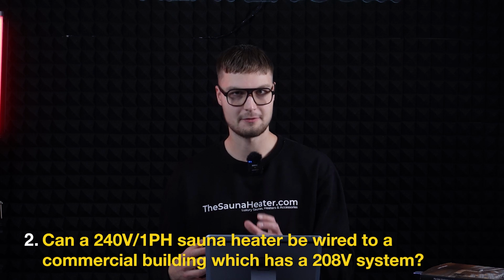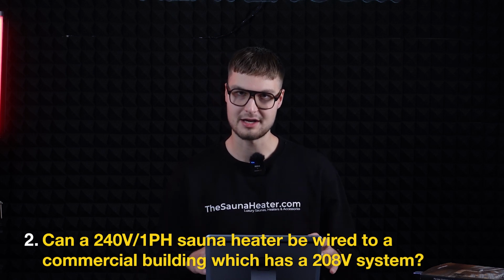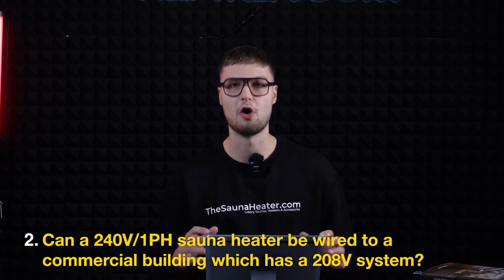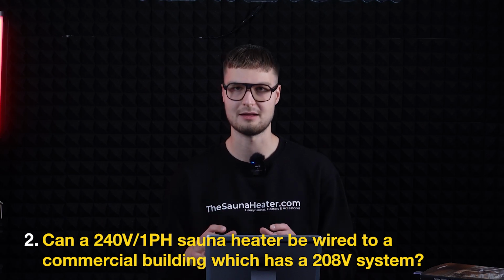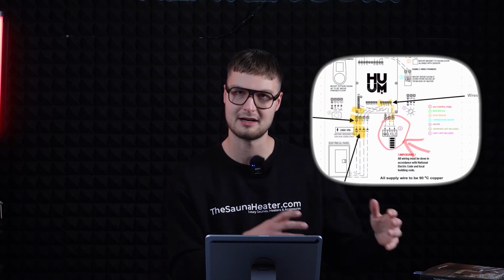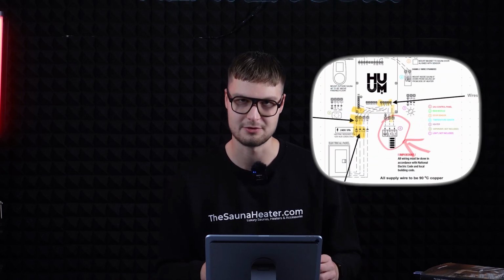Second question: can a 240 volt one phase sauna heater be wired to a commercial building which only has a 208 volt system available? The answer is yes. You can wire a 240 volt one phase electric sauna heater for a commercial building with 208 volts by using just two hot wires, L1 and L2, from the 208 volt three phase system. This reduces the sauna heater's power output by 25%, which you need to account for when sizing your sauna heater.